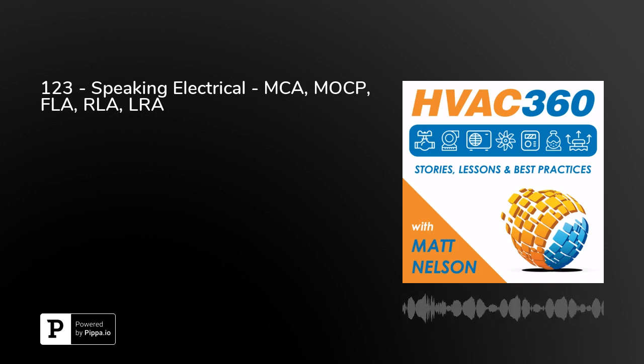I guess one of the terms that we're going to be talking about today that is all over the board, you're going to see it pretty much everywhere, and that is FLA, which stands for full load amps. Now, this is the amount of continuous current that a running motor, remembering it's running, not starting, and that's a critical component, will consume when it's running at its maximum load. So FLA, full load amps. And why is that important? Full load amps is one of the things that electrical engineers use to size conductors, equipment, pretty much everything. So FLA is kind of a standard building block that they use.